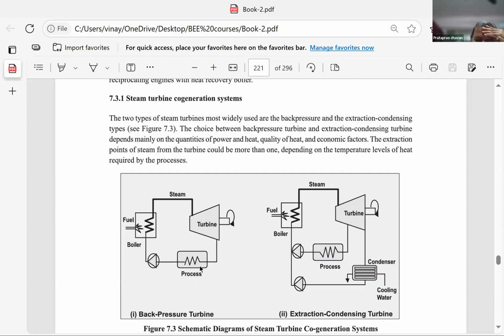In the industrial process, heat will be imparted to the industrial product, and the cooled steam, which is converted into water, goes to the boiler. So thereby we are recovering the waste heat of the turbine steam, which is the exhaust steam, allowing it to exhaust at higher pressure and temperature, collecting it for process purposes and recirculating. This is called a back pressure turbine.